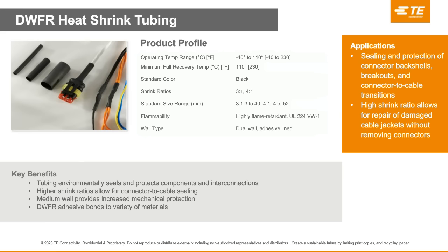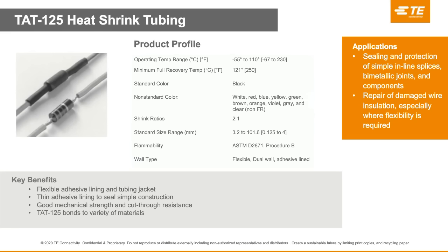Our DWFR, or Dual Wall Flame Retardant heat shrink tubing, is another adhesive-lined, medium-walled, highly flame retardant tubing product with a high shrink ratio. Our DWFR meets the VW-1 flammability rating — the vertical wire test — which is one of the highest ratings in the industry. Finally, the TAT125 heat shrink tubing has a flexible adhesive lining and tubing jacket, making it ideal for simple sealing of inline splices, bimetallic joints, and components. It has good mechanical strength and cut-through resistance, and comes in a variety of colors with a standard 2-to-1 heat shrink ratio.